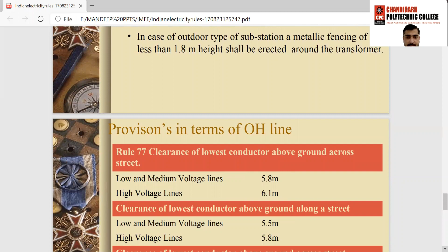Provisions in terms of overhead lines. For overhead lines, to transmit the energy, there are some rules. Rule 77: clearance of lowest conductor above ground across street. For low and medium voltage lines, the ground clearance across the street should be 5.8 meter, and the ground clearance for high voltage lines should be 6.1 meter.